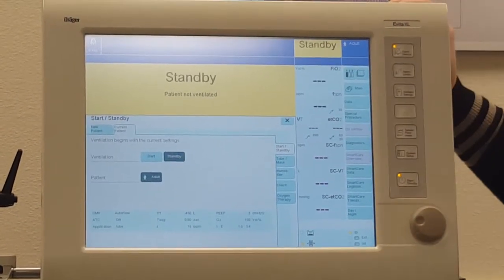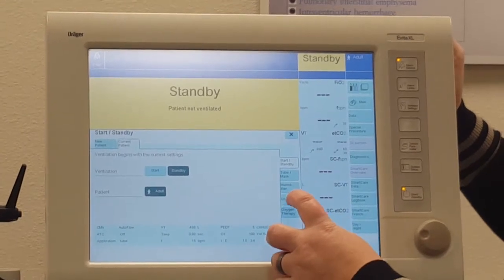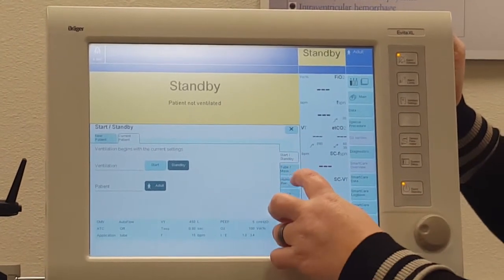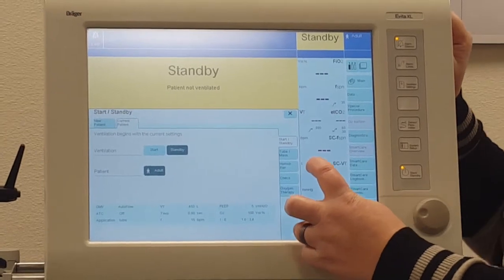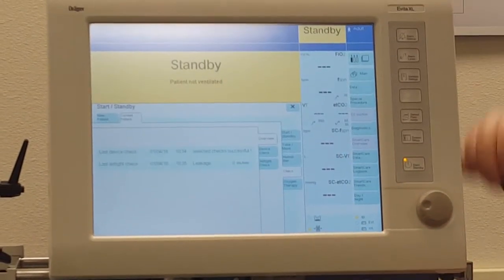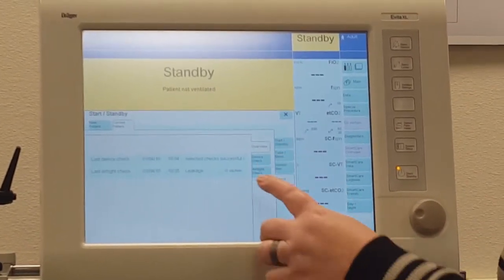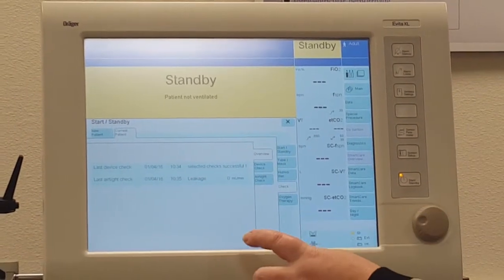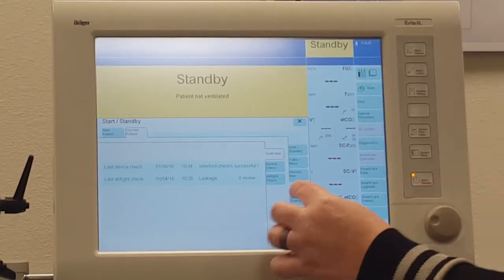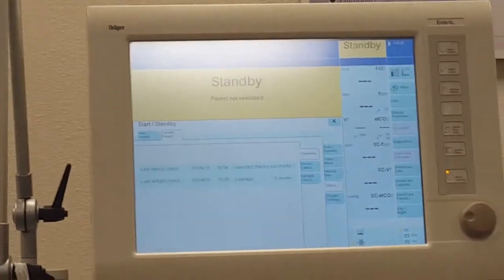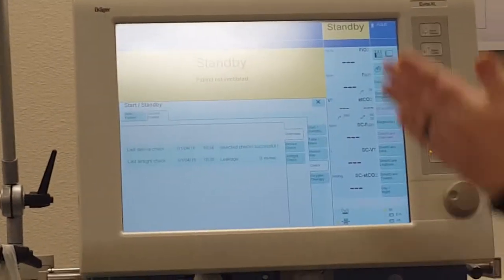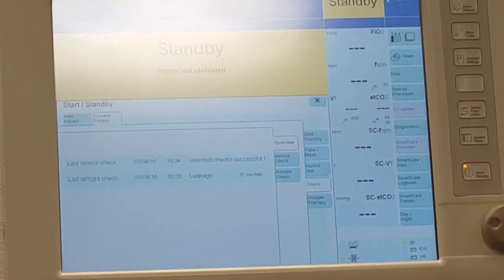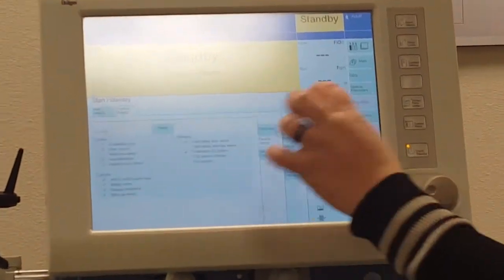Once you're on this screen, you're going to see the word check. It's 1, 2, 3, 4 spots down right here, so push that. Once you push that, you'll see an overview which tells you when the checks were done last. And then you're going to see device check and airtight check. Those are the two different checks that have to be done on this ventilator. The device check is the overall calibration of it. The airtight check is the one that tests the circuit to make sure there's no leaks in it. So we're going to hit device check first, and then we're going to hit the word check.